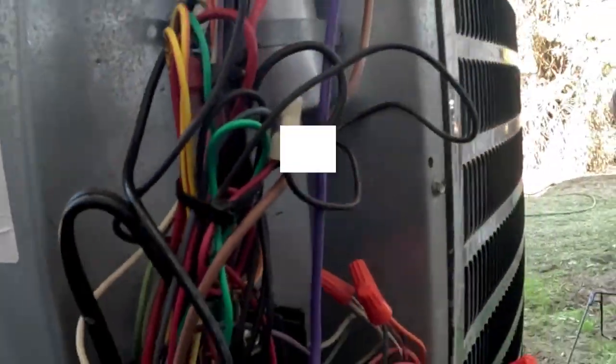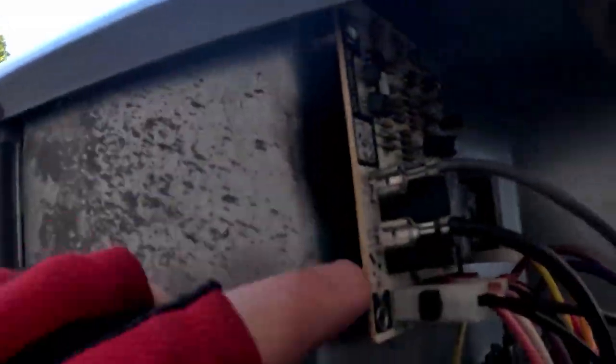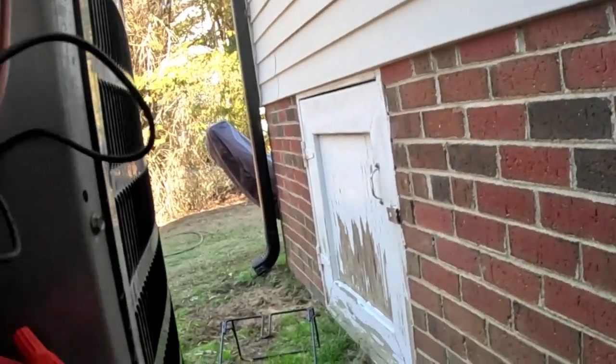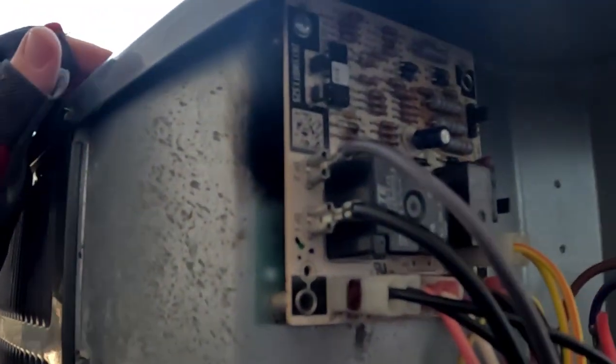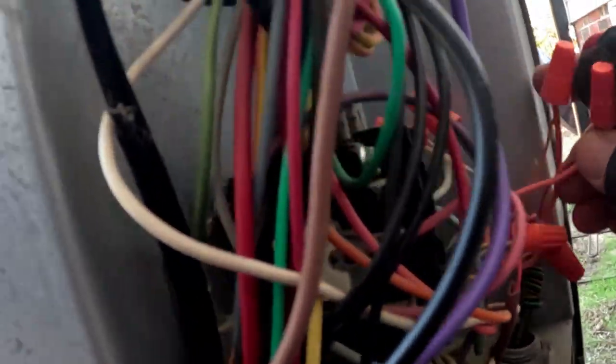We're looking at a Goodman unit. One of the guys was here this morning and the back of the defrost board was arcing right there against the cabinet interior of the unit. He left the disconnect out. We called to order a board and they didn't have any — said we can get one tomorrow. We left the disconnect off, and go figure, it's going to be 75 degrees this afternoon. We want to get this guy some air conditioning while he's waiting on that board. You can bypass these and still run the system — you're just not going to have defrost. It's not going to get below 50 tonight so we should be okay.